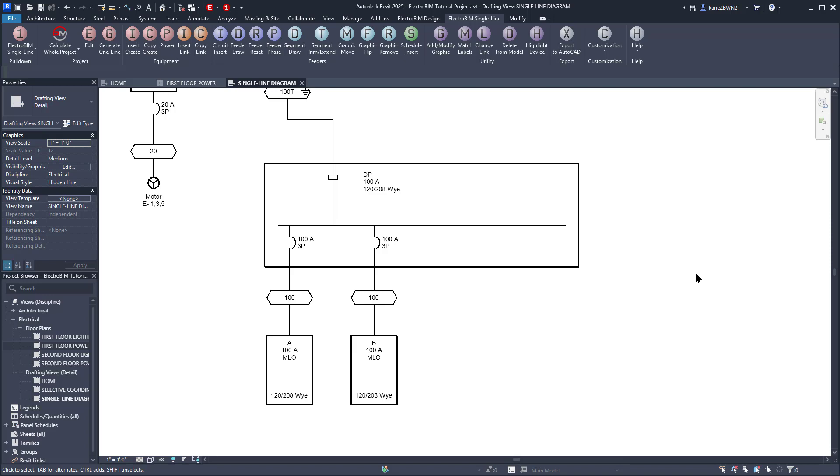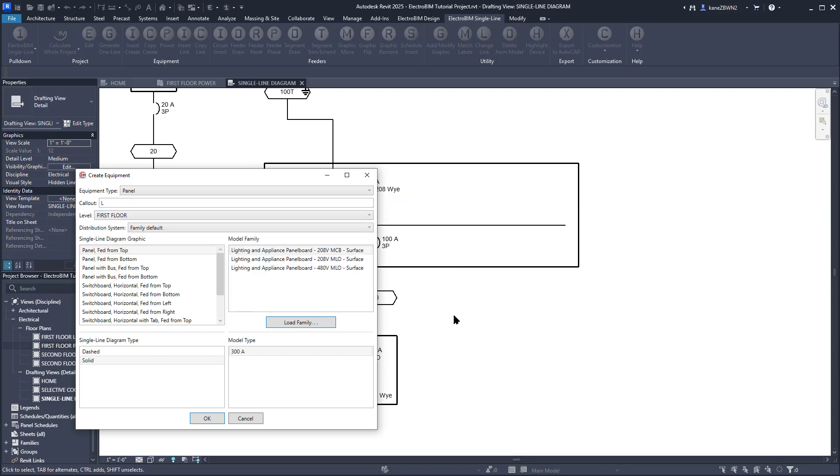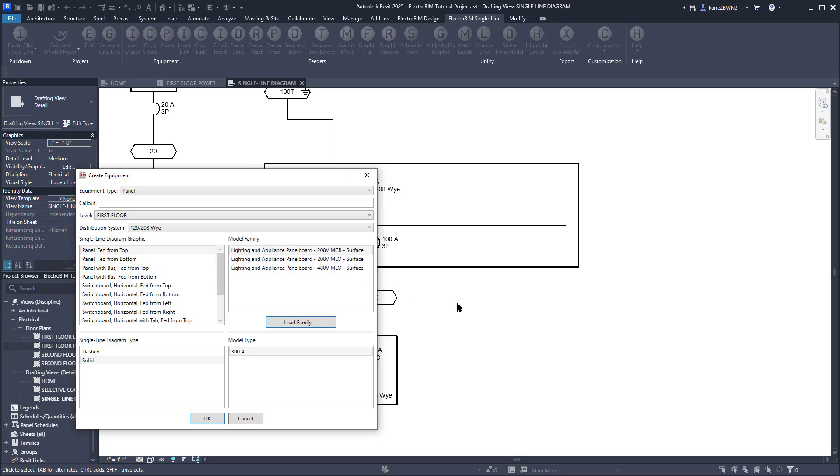With this command, you can create a new device in the model, insert it on the single line, and circuit it without having to leave the drafting view. So we'll set the Callout to L, set the Level to 1st Floor so we can put it in the electrical closet, set the Voltage to 120208Y, select this 208 MLO panel family, and press OK to create the panel.